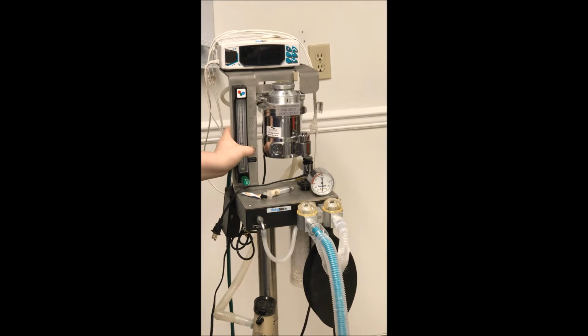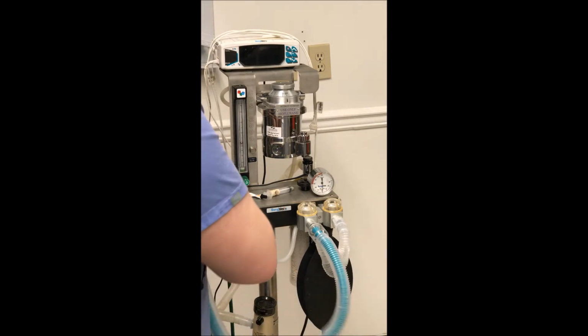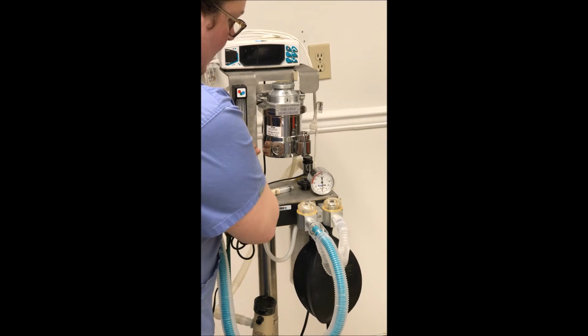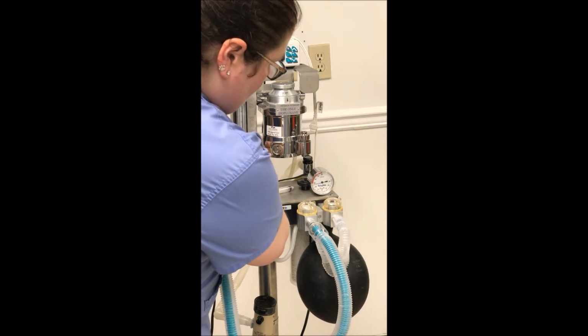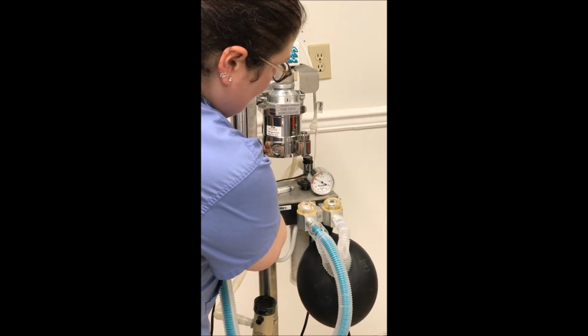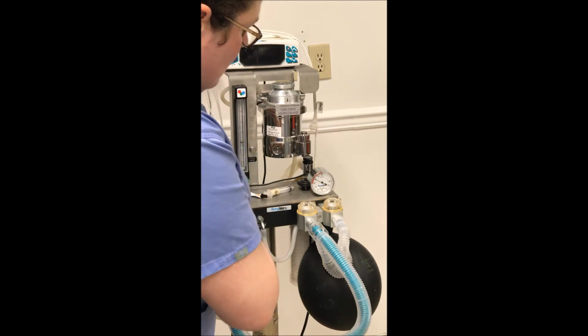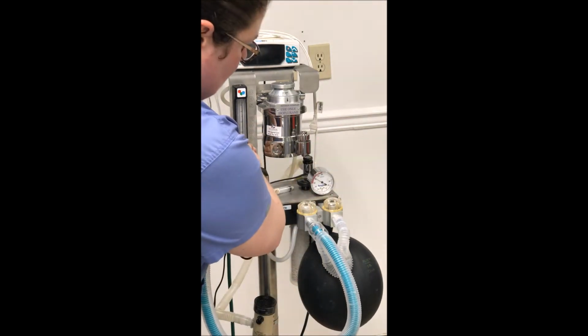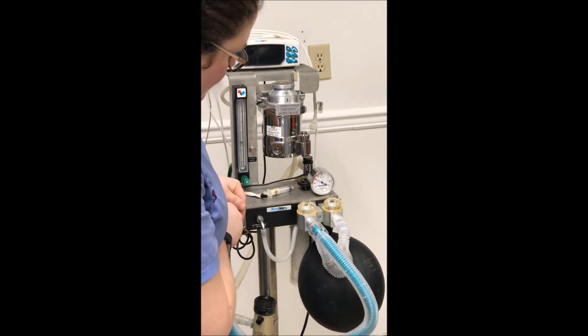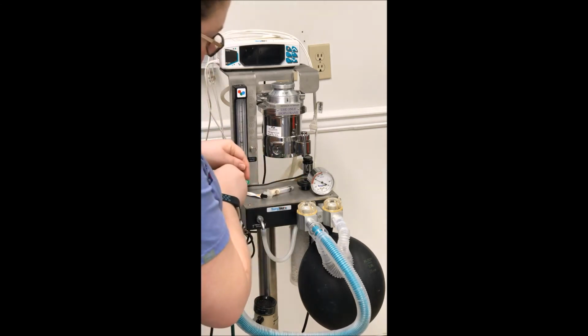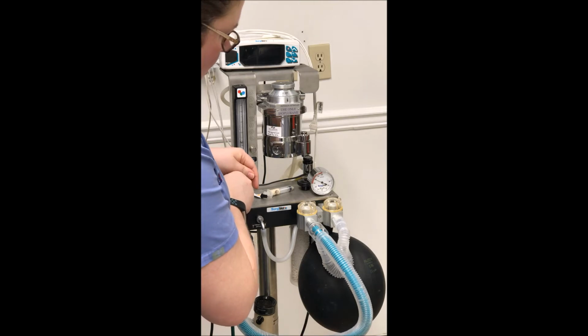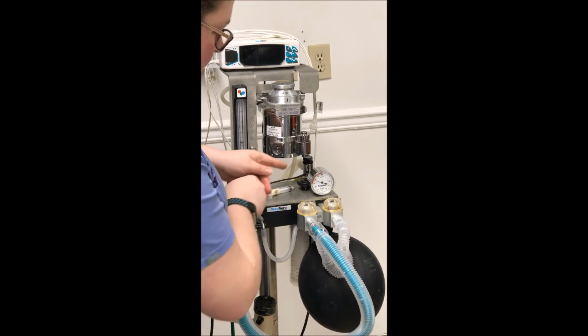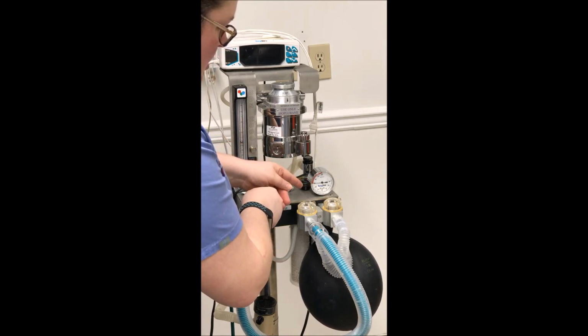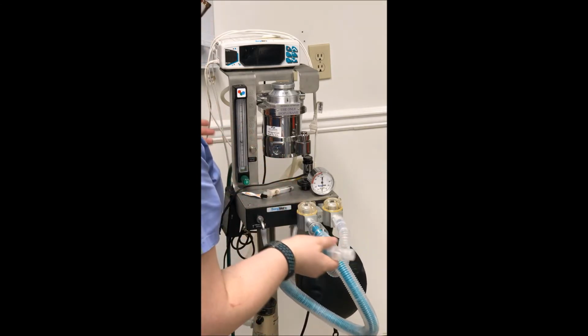Leak check on the machine. We're going to close our pop-off valve. We're going to fill our reservoir bag with oxygen. And we want to fill it until our pressure manometer gets to about 40. And I have it blocked here. So we want to hold it, and as long as the gauge stays at 40, we're good and we have no leaks. And I can slowly release my hand. As you can see, it will drop then. So we are leak free.